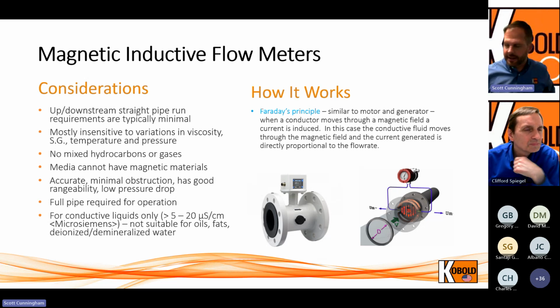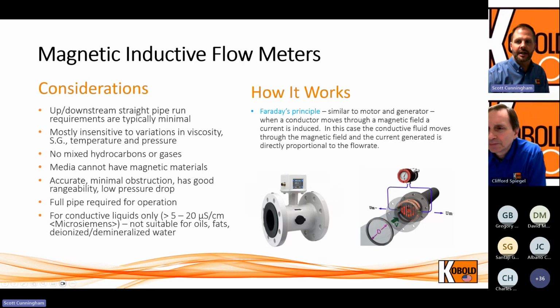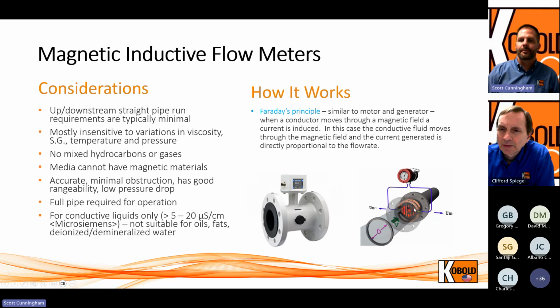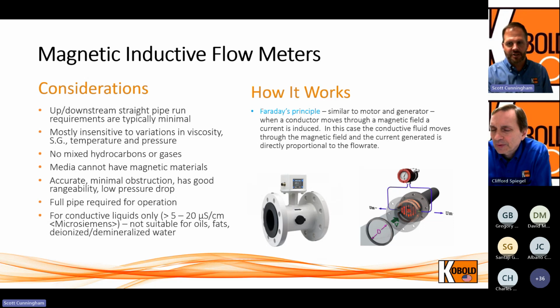The reason behind that is how it actually operates—similar to a motor and a generator. When the media moves through, there's a magnetic field, and as that conductive media moves through the field, a current is induced. That current is directly proportional to the flow rate, or really the velocity, as Cliff mentioned before. As velocity through the pipe increases, the current increases proportionally. We then use that velocity with the area to calculate the volume over time—the flow rate.